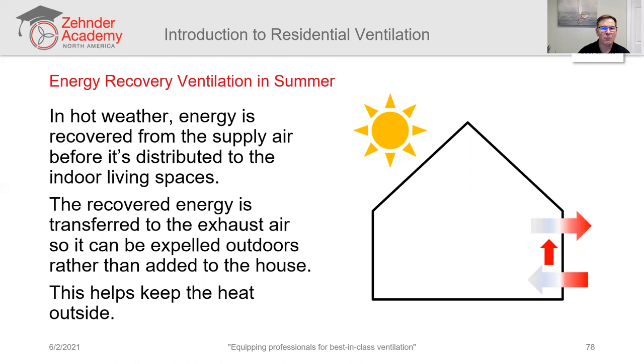In the summer, there's a couple of ways of talking about recovery. Sounds wrong because you're not trying to recover heat. You're trying to transfer heat before you bring in supply air. So you're transferring heat from the supply air coming in from outside over to the exhaust air and exhausting that excess heat with your exhaust air. Some people call this cold recovery. It's inaccurate because cold isn't a thing. Heat is a thing. But in any case, the physics of it are the same. Heat is moving by conduction across the medium inside of this appliance, and it's moving between the two air streams.